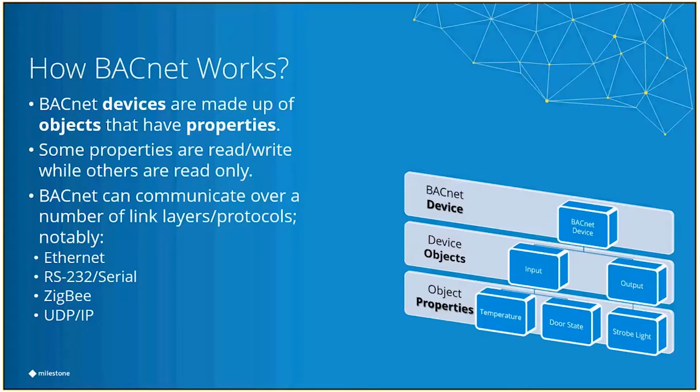Another thing I found interesting was how BACnet networks work. They can work over traditional TCP/IP networks. However, Ethernet networks are identified by MAC address only, so they require things like BACnet routers or BACnet gateways. We can also incorporate it into something called Modbus, which is supported on a BACnet network through BACnet gateways. But we actually have a Modbus plugin for XProtect as well, so I thought I would mention that.